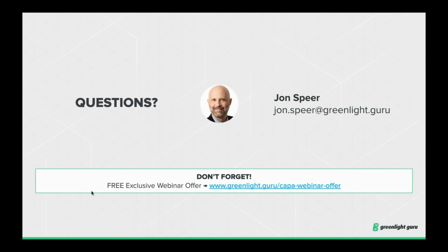All right, so Christina asked, what is the difference between CAPA and nonconformance procedures? And I'm going to speculate a little bit about where Christina might be going with this. Technically speaking, if I go through an audit and something about my practices does not comply with the regulatory requirements, then that can be viewed as a nonconformance. When I was speaking about nonconformance earlier, I specifically intended to focus on non-conforming products. So I go through my manufacturing process, building my device per my defined specifications, and during the manufacturing, my product fails to meet that defined specification. Well, that would be a candidate for a non-conforming product. So I know sometimes the words get used in multiple different scenarios.